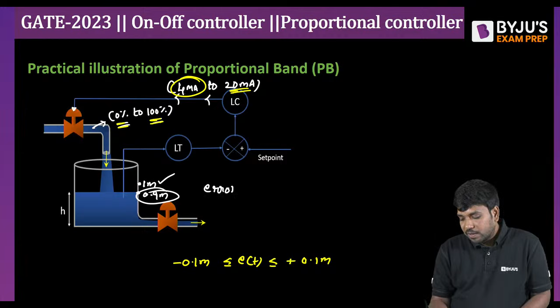So when the error is 0.1 meter, immediately it will generate 20 milliampere current. When 20 milliampere current is generated, the maximum possible opening will come out of the valve, that is 100%. So suddenly the input flow rate will be so high, right? The water level will jump so much here, right? Because the opening is so much, the water level will suddenly go up.